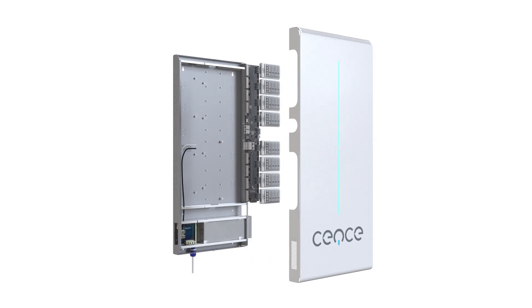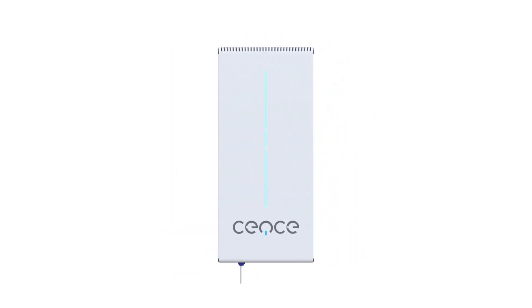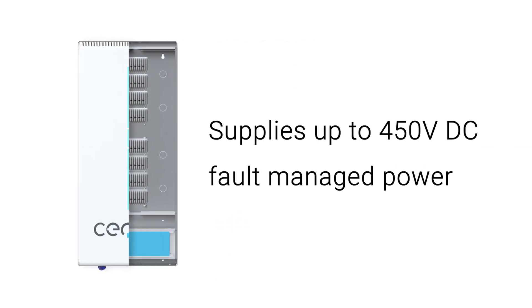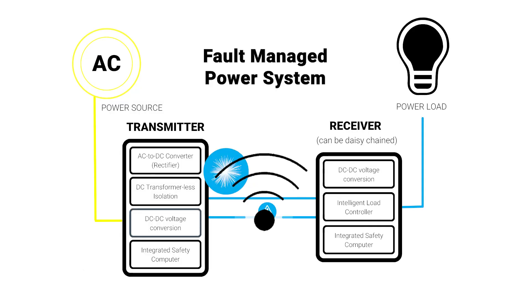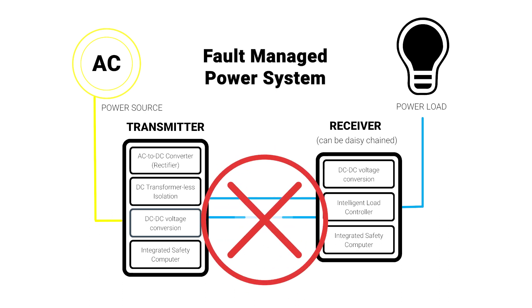Enter Cence. With Cence you can get flexible high and low voltage DC power systems. Cence HVDC or high voltage DC supplies up to 450 volts DC and is fault managed, meaning it is intelligent enough to understand when faults occur, including human contact. When any faults are detected, power is shut off immediately, making it virtually free of all shock and fire hazards.